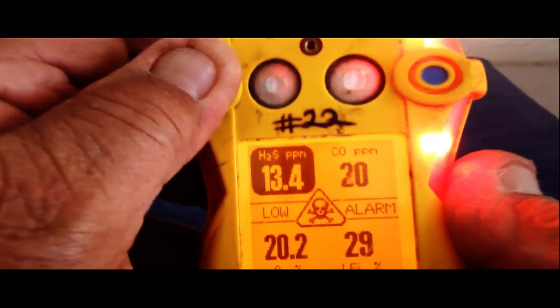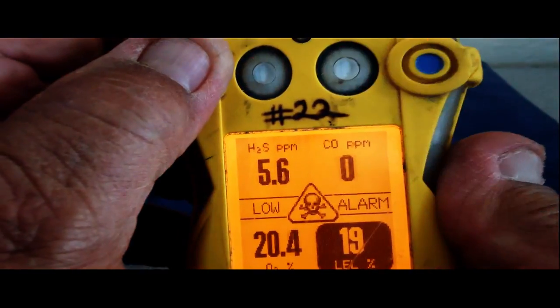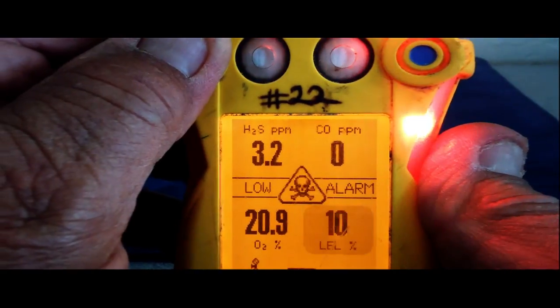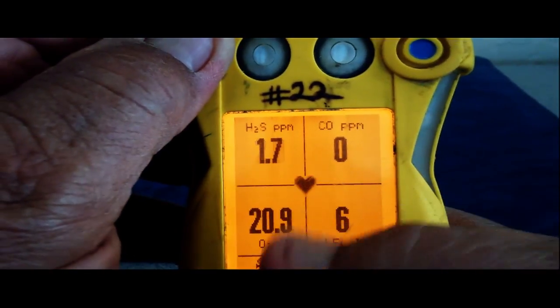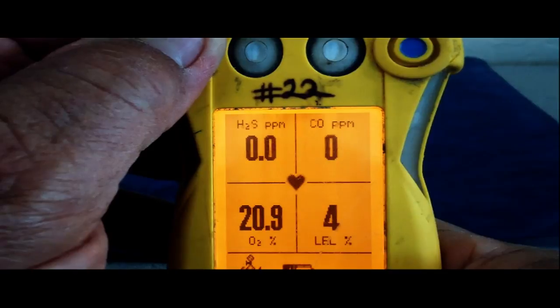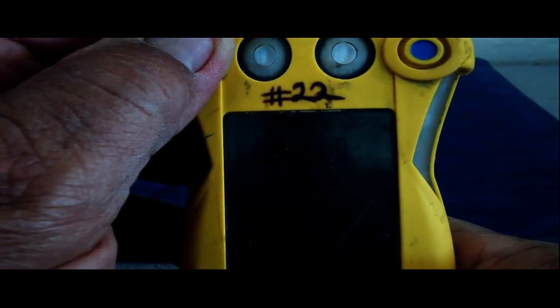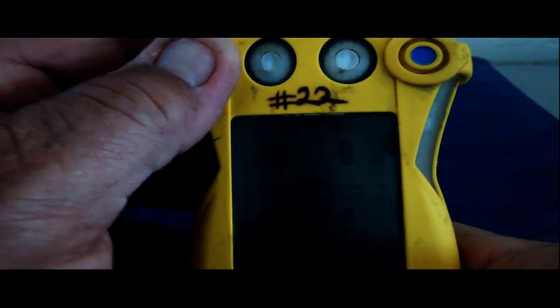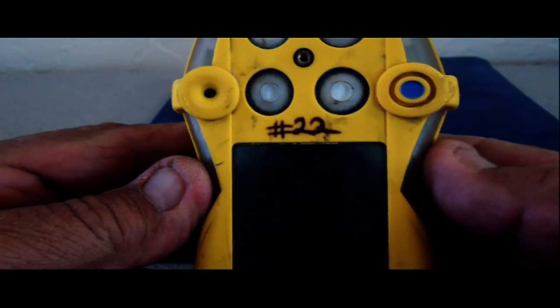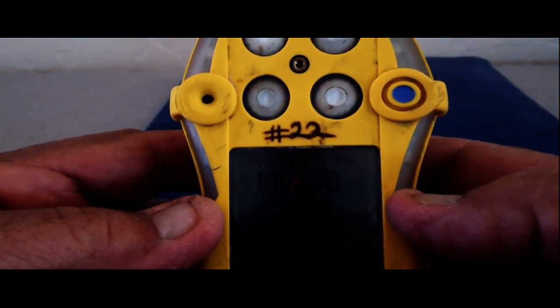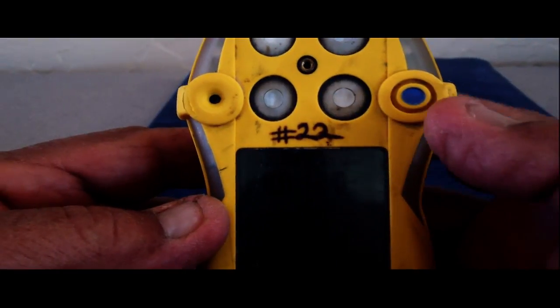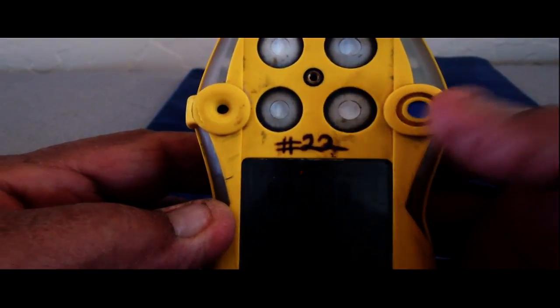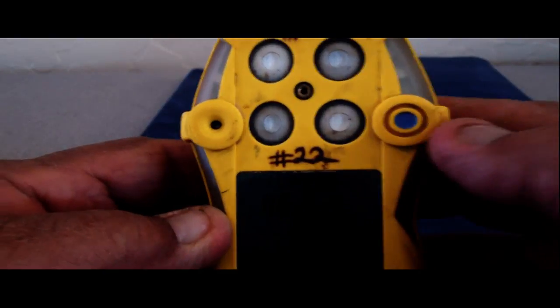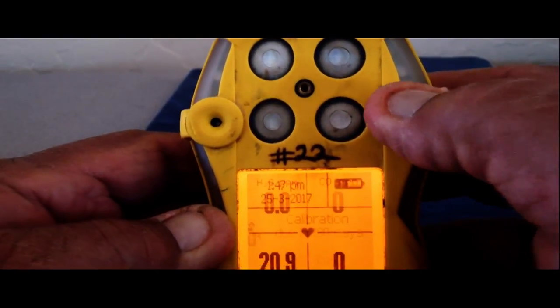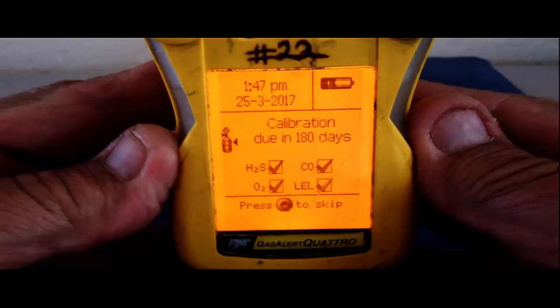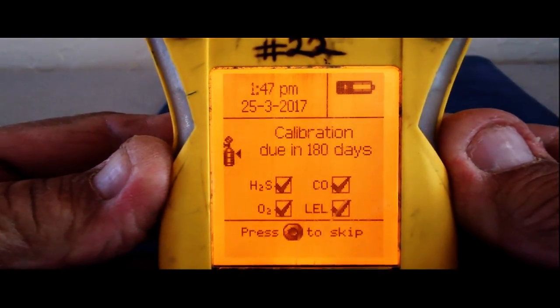It seems that these sensors wake up once you show them some gas. So we're going back to zeros. It will alarm like that until you get back into the acceptable entry conditions for these sensors. Since we've done that, let's go to the peak mode. Since I showed it gas, it should give me a reading on the peaks. To get to my peaks, I push that button twice, rapidly, once, twice, and there we go. We're back in the peak mode.